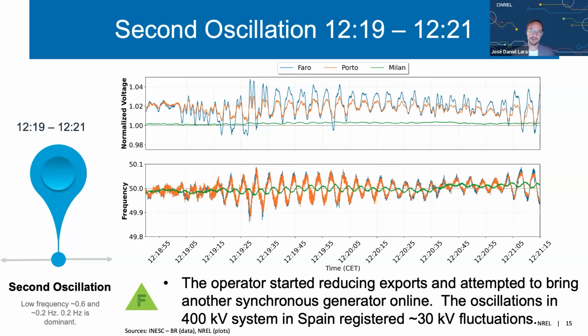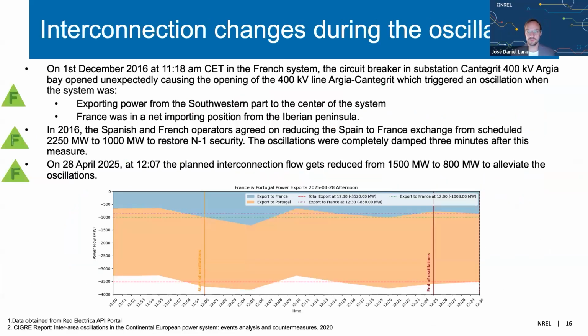So the question we had was, after this oscillation happened over those 12 minutes, what actions were taken that could have driven some of these situations? We'll look at the changes in the interconnection. As I mentioned, in the 2016 event the operator reduced the interconnections. This is from the 2016 report, where it was brought from 2,250 megawatts down to 1,000 megawatts to essentially restore and reduce that. And on April 28th, the interconnection flow gates were reduced to 1,500 to 800 to alleviate these oscillations.